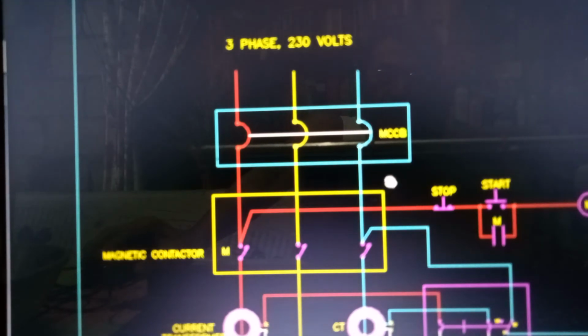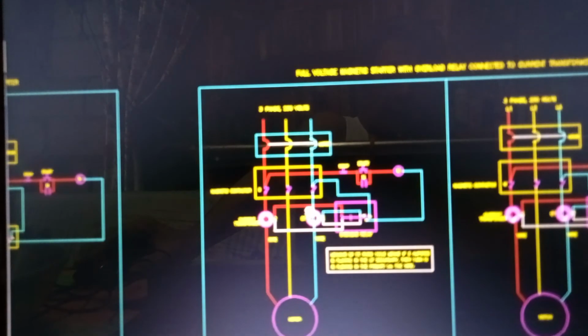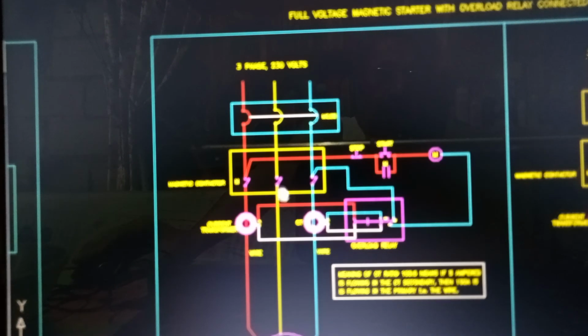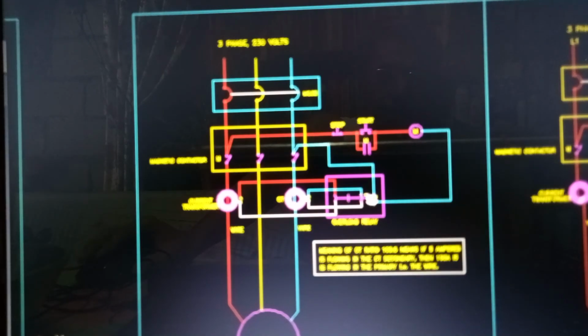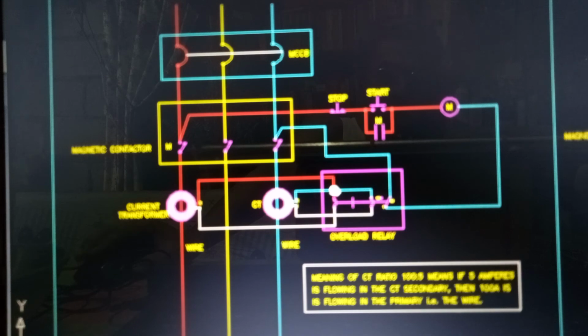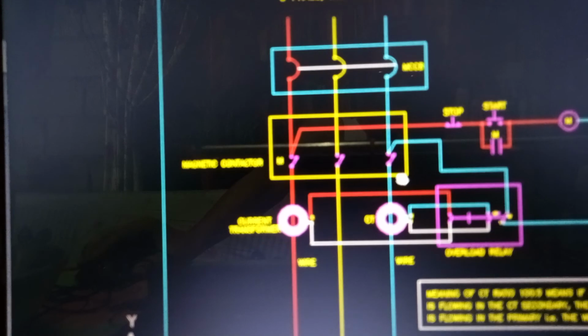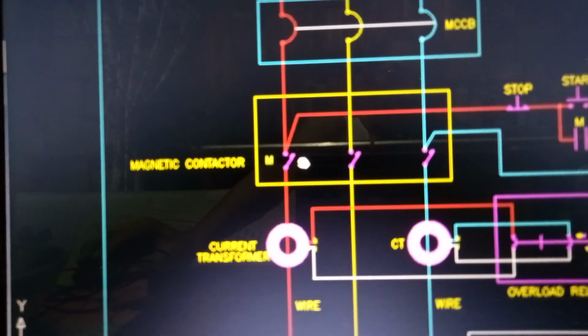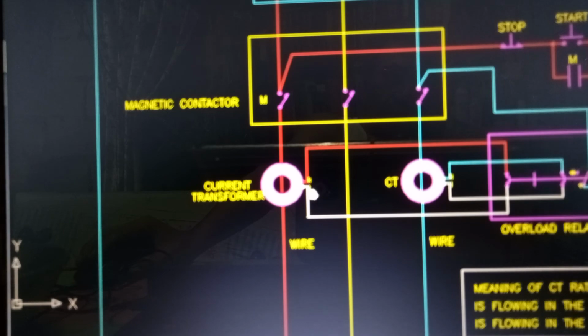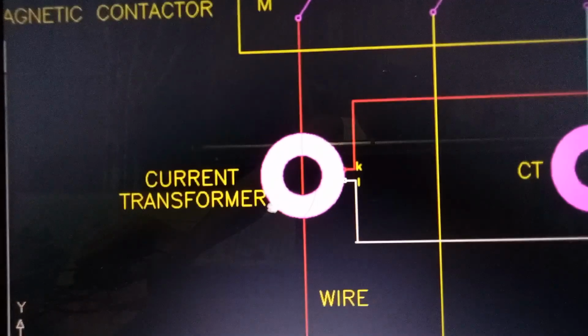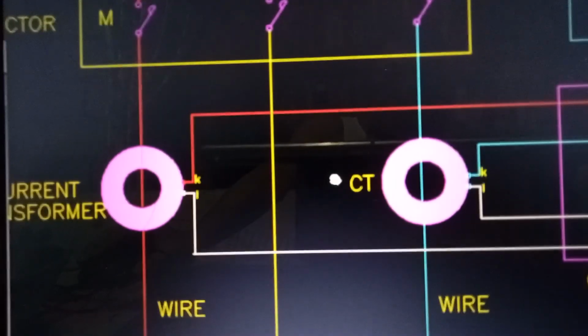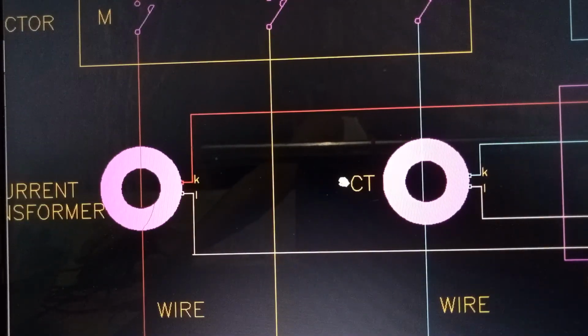So we have here the power circuit of the current transformer on the left side, and on the right side is the schematic diagram of the full voltage magnetic starter. We have here the molded case circuit breaker, magnetic contactor, and then connected on line 1 is the current transformer, and on line 3 there is also another current transformer. There is no CT on line 2.